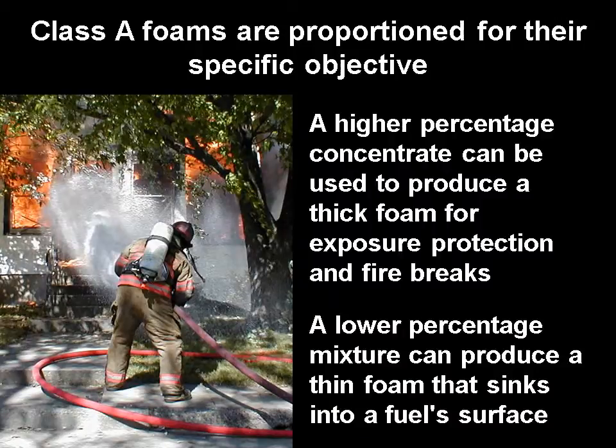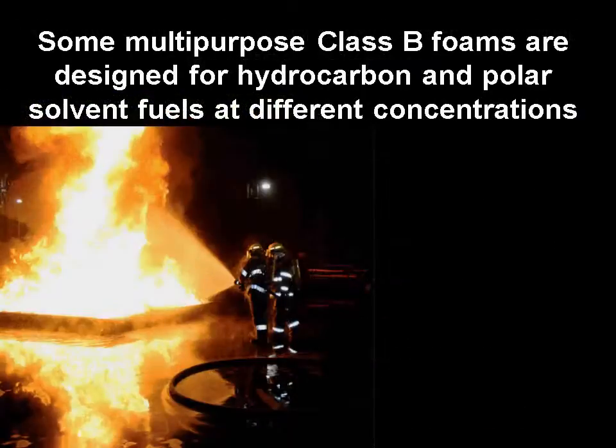Some multi-purpose Class B foams are designed for hydrocarbon and polar solvent fires at different concentrations: 3% for hydrocarbons, 6% for polar solvents.